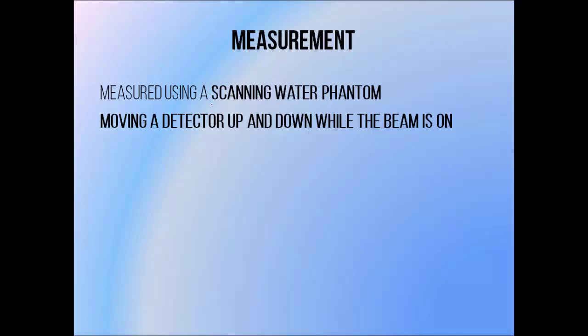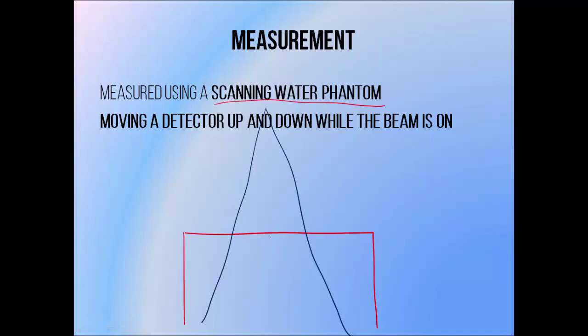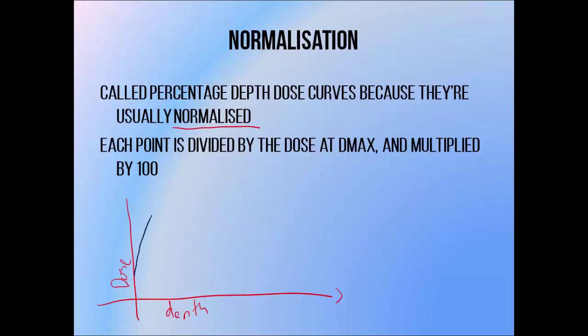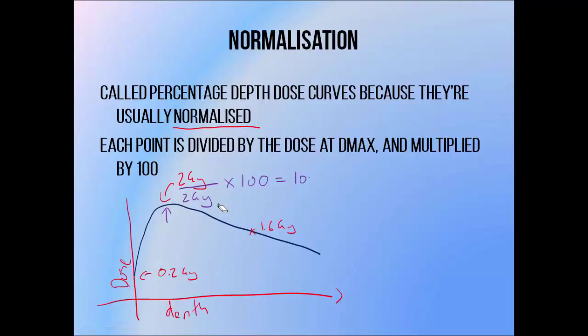Depth dose curves are generally measured using a scanning water phantom. They are obtained by moving a detector up and down and measuring dose while the beam is on. This allows us to determine how dose varies with depth in water, which we class as equivalent to patient soft tissue. We call them percentage depth dose curves because they're normally normalized by choosing one point on the curve, normally the depth of maximum dose, or D-max, and dividing the dose at every depth by this dose and multiplying by 100.